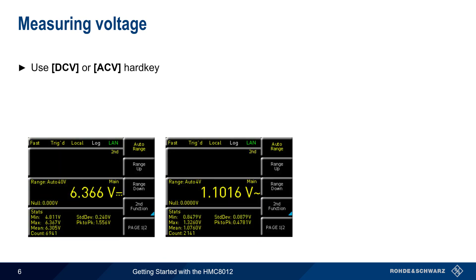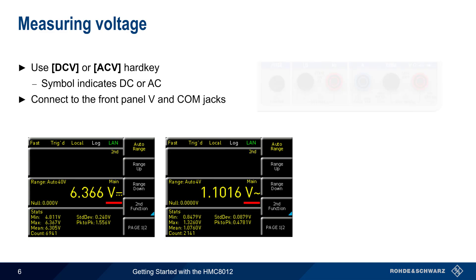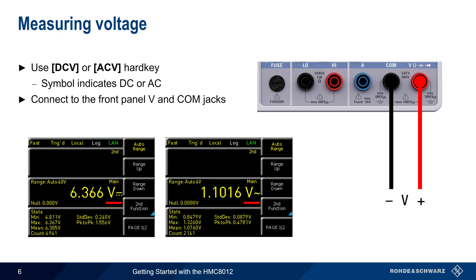Voltage measurements are made by pressing the DC volts or AC volts hard keys. A special symbol behind the V indicates whether DC or AC is being measured. On the front panel, the V and COM jacks are used to connect to the measured voltage. Note that AC voltage measurements made by the HMC 8012 are always true RMS voltage values, which provides an accurate value even for non-sinusoidal AC signals.